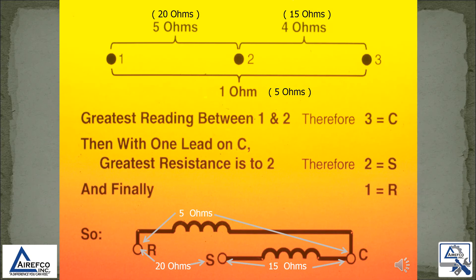The greatest reading is between terminals 1 and 2, which would be our run and start terminals, and that would be 20 ohms. Therefore terminal 3 is your common lead. Then with one lead on common, the greatest resistance is terminal 2, which is the start winding at 15 ohms. And finally terminal 1 is our run winding, which is the least resistance of 5 ohms.